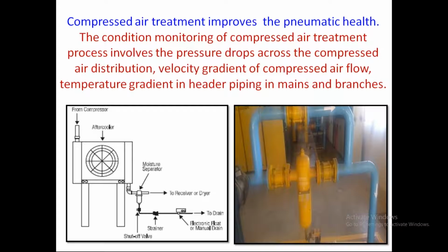So the water separator or the moisture separator has to be kept outside the compressor hood, and that has to be monitored correctly. If the moisture separator is not operating correctly, automatically you will find more energy loss in the system. It is an aggravated energy loss. You can see the NPTEL's flow chart. It says the moisture separator has to be kept after the after cooler, and it is kept visible to the operator. Daily he has to see that the moisture separator or the water separator is functioning well.